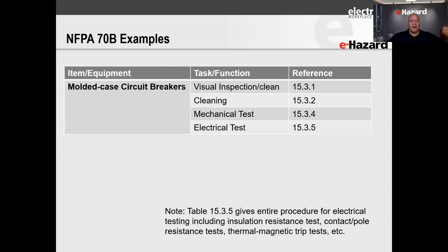Then we take that back and go to the chapter 9 table to get our interval. If there are intervals different than chapter 9, they'll be in the specific article - transformers is one example, where we're sampling insulating oil to monitor moisture content and how that's going. So that table's a little different than what we have in chapter 9.